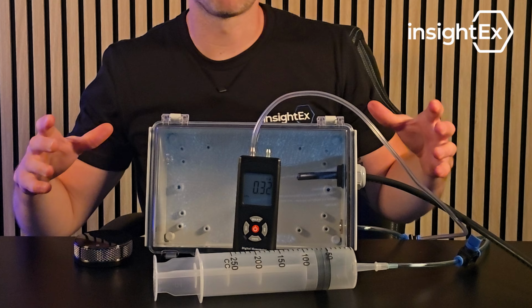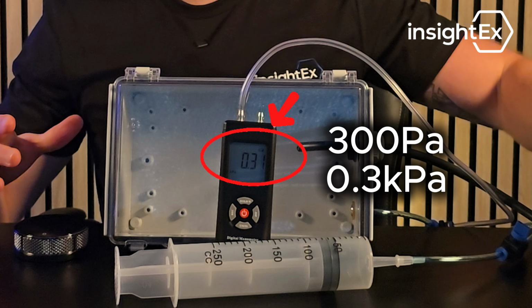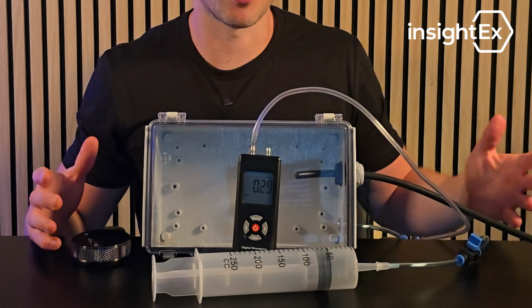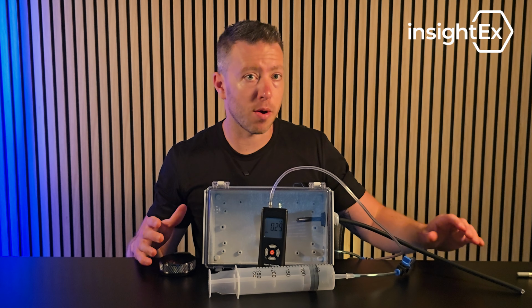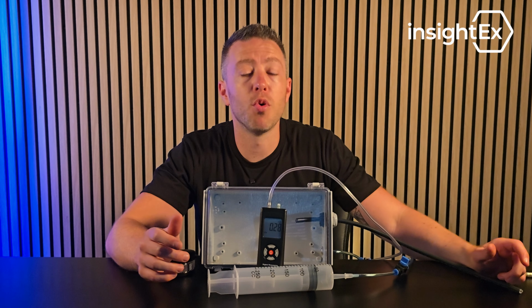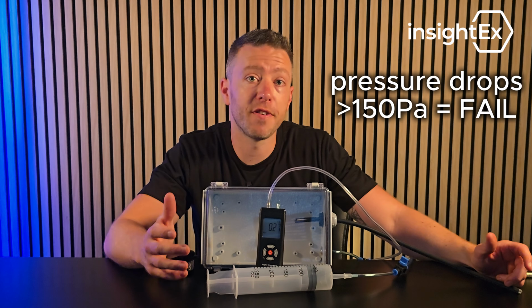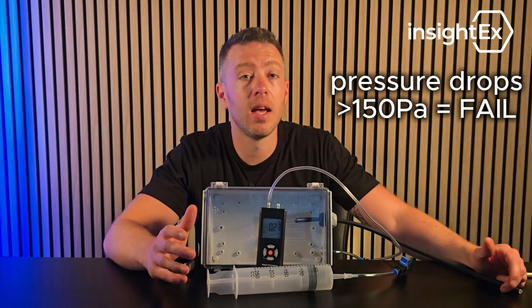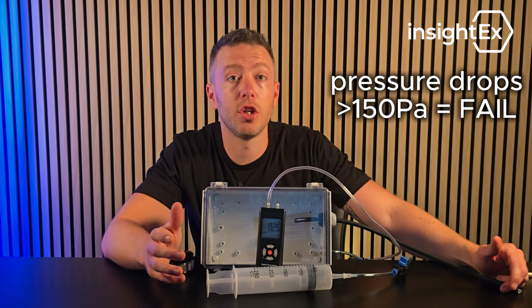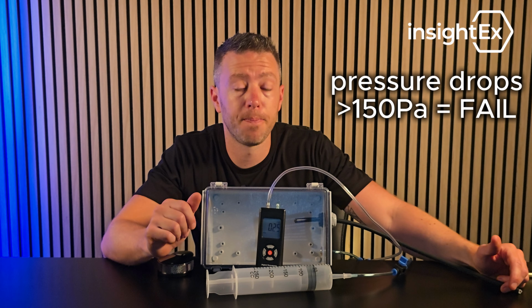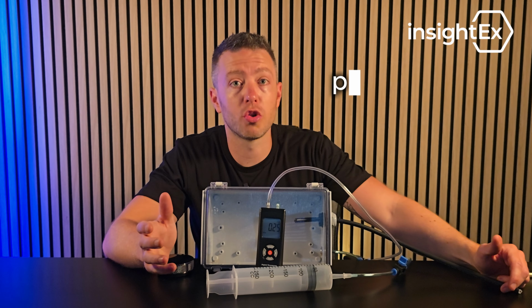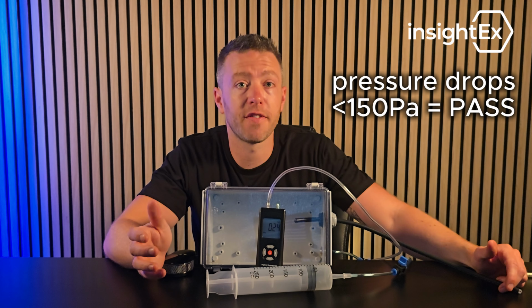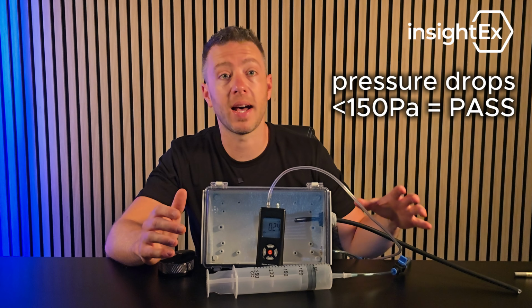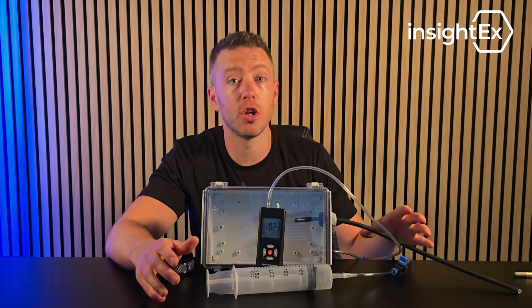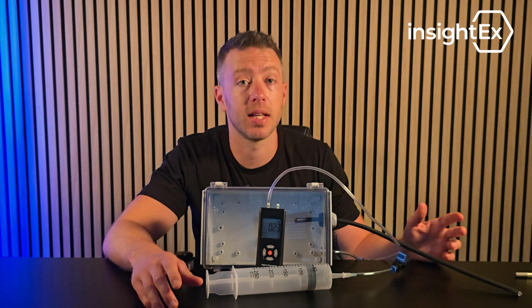So you apply a pressure of 300 pascals to the cable, which is a really low pressure, and then you monitor the pressure drop. If the pressure drops more than 150 pascals or 50% in 5 seconds, then that's a fail and you'll need to use a barrier gland for this type of cable. If the pressure holds or drops less than 150 pascals over 5 seconds, the cable has passed the test and you're probably good to go with a standard elastomeric seal.